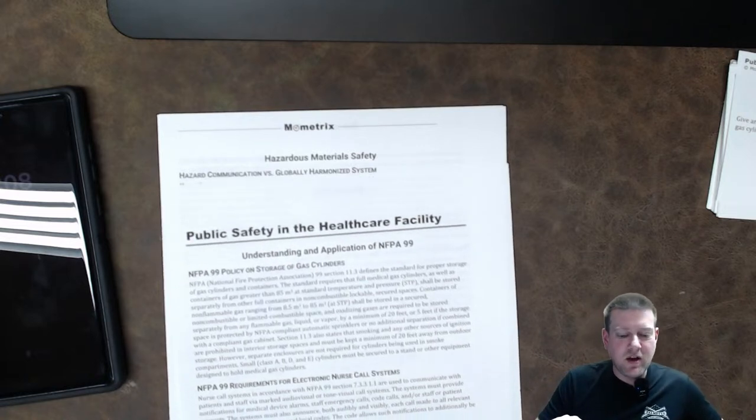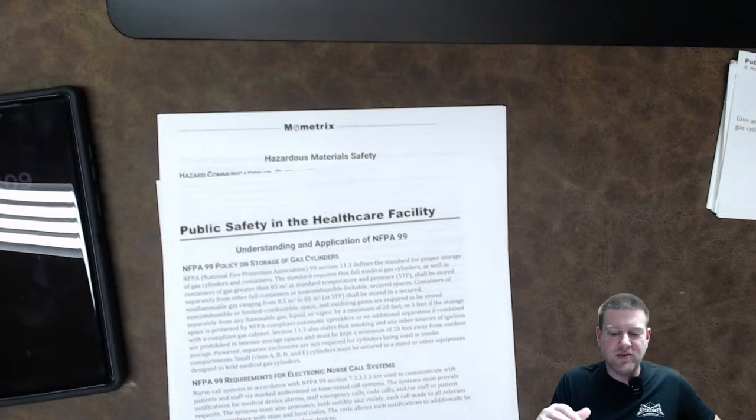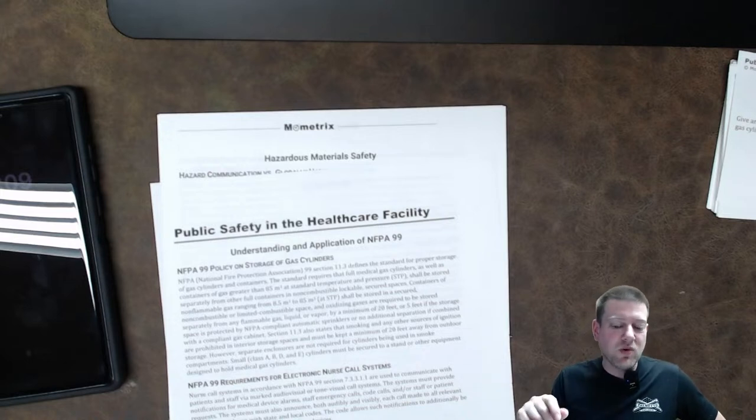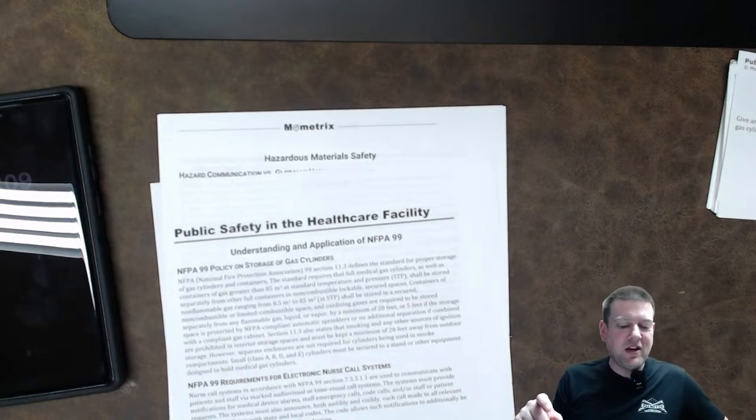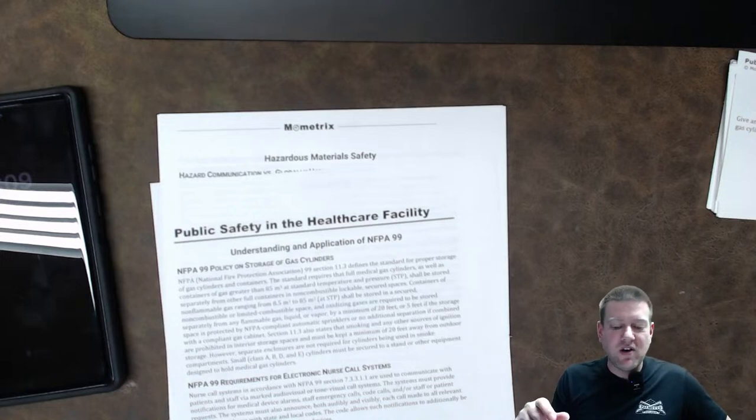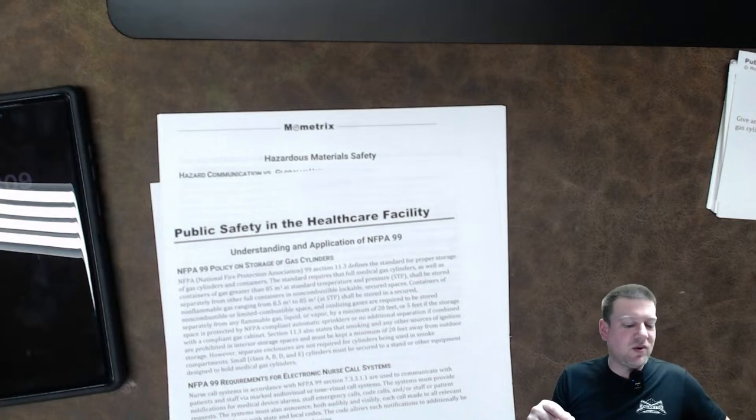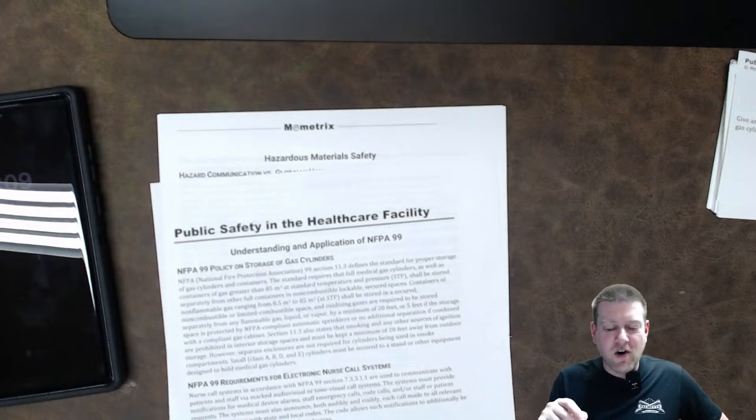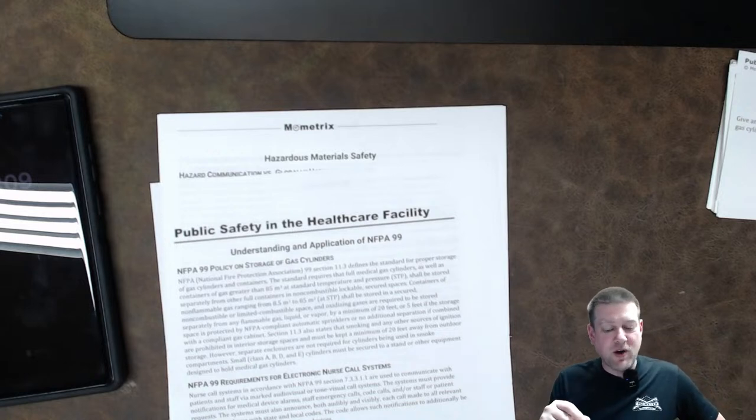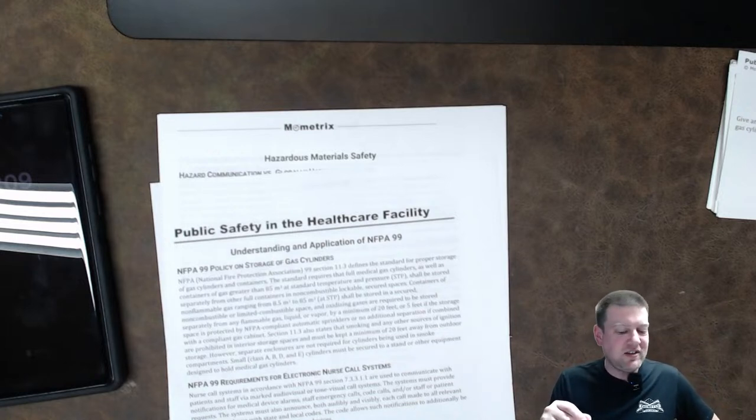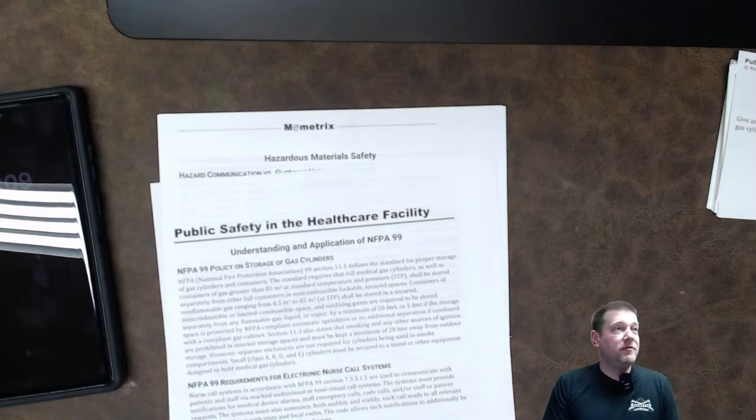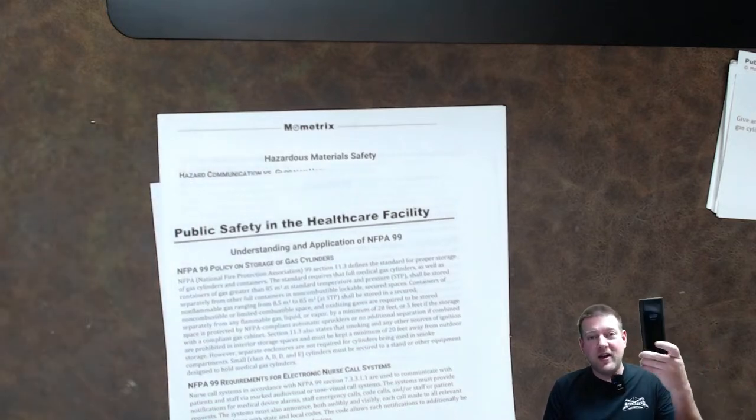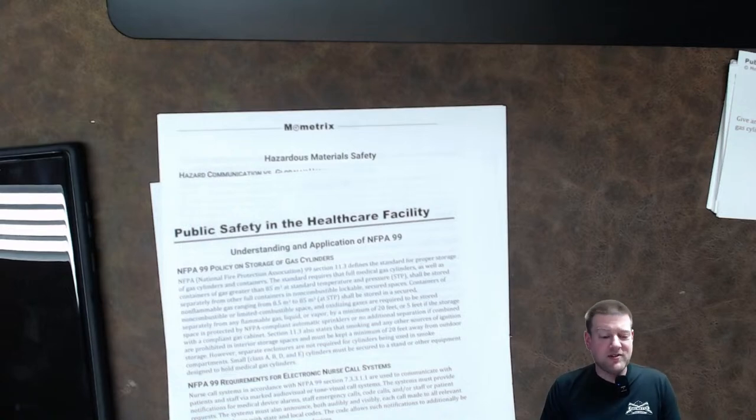NFPA 99 requirements for electronic nurse call systems. Nurse calls, in accordance with NFPA 99, Section 7.3.3.1.1, are used to communicate with patients and staff via marked audiovisual and tonevisual call systems. The systems must provide notifications for medical device alarms, staff emergency calls, code calls, and or staff or patient requests. The systems must also announce, both audibly and visually, each call made to relevant areas in accordance with state and local codes. The code allows such notifications to be additionally sent to staff via pagers and other wireless devices. There is some really interesting new tech coming out for nurse call systems that allow it to page to, like, on-call cell phones and stuff. Some pretty cool stuff.